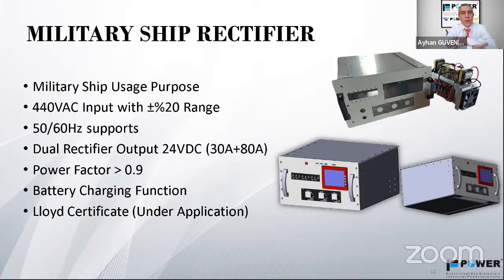The input voltage is 440 volt AC with plus minus 20 range, and it supports 50 and 60 Hz at the same time. The output is 24 volt DC dual output, 30 and 80 amps. The input power factor is more than 0.9. These products feed the DC loads and at the same time charge the batteries - it has a charging function also.